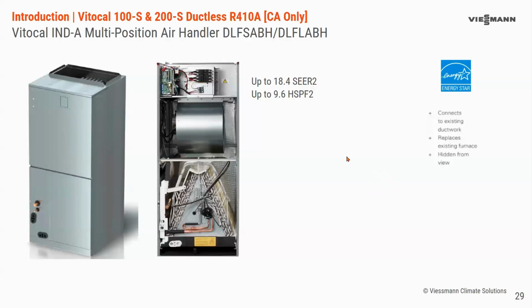So you're still going to get high efficiencies on this, but there's some efficiency loss due to the coil size with this unit. It's available from 18,000 to 60,000 BTU. However, there are some asterisks on that, with the 36, 48, and 60,000 being the light commercial air handlers. So depending on your application with the ductless, you may be limited to a 36,000 BTU, which is why we would step up to what we're going to talk about next shortly, the ducted heat pumps.